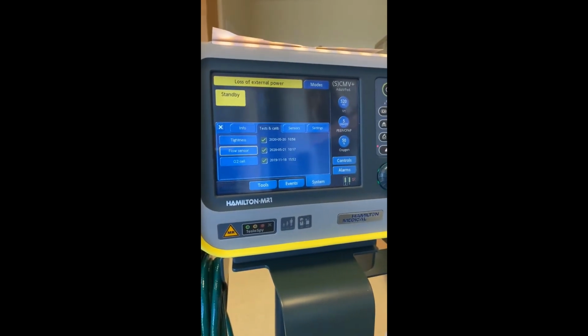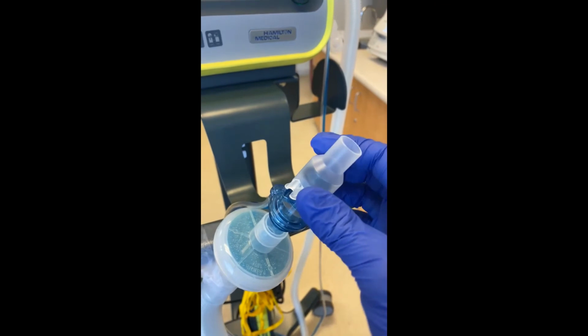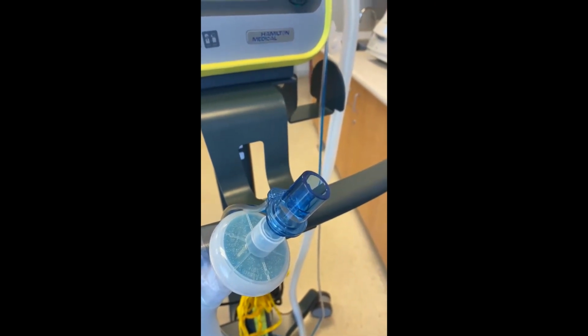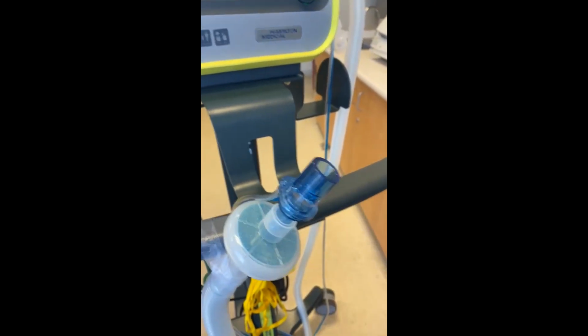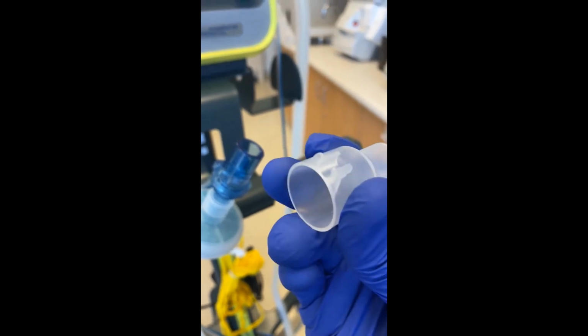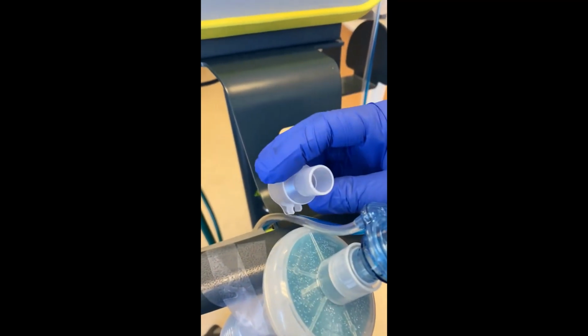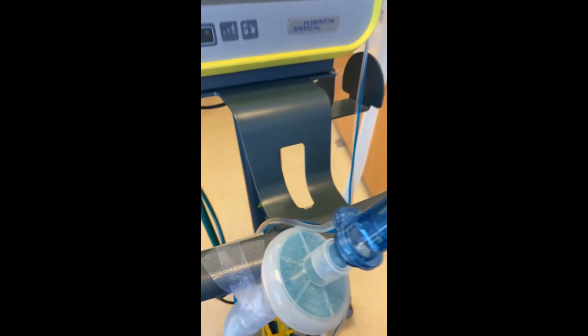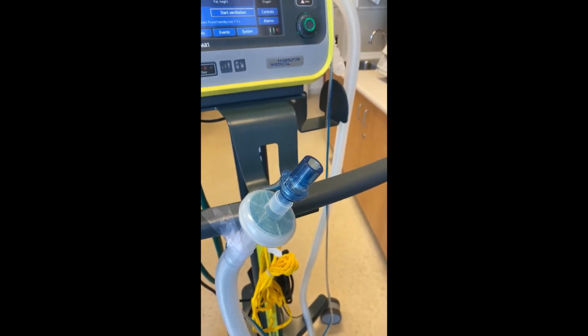the process again. And when it's done, you won't need this adapter piece, so you need to take that off. This is what actually goes to the patient, and then it comes with this little piece here that can snap right onto your tubing, and that way you don't lose it. And that is how you do a flow sensor check.